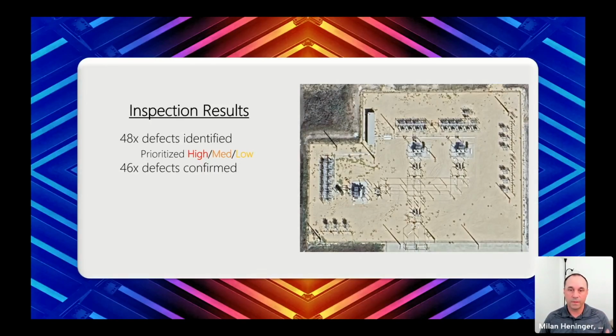They found something that was on the bushings. They found loose connections. They found other issues in that substation and were immediately able to confirm it. That means we had a 96% hit rate, and all of the high and medium risk defects were confirmed and corrected.